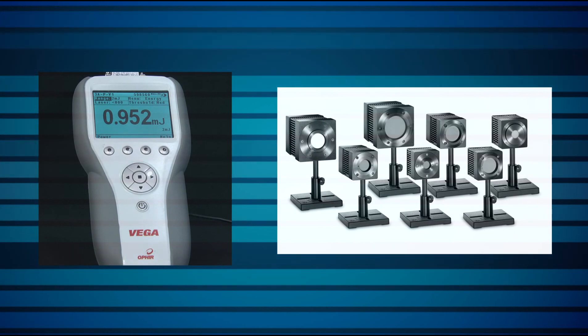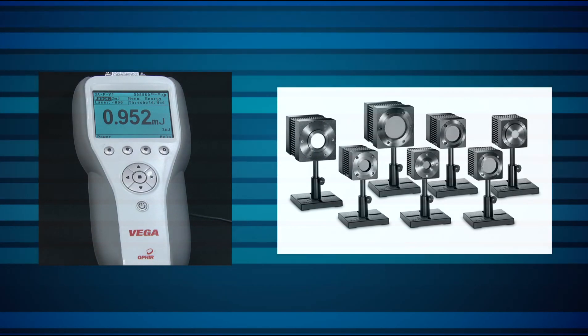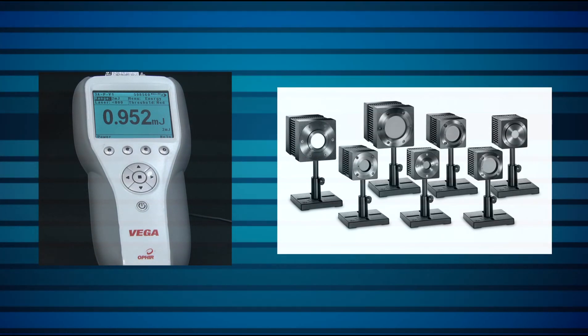But with many tens of joules per square centimeter zapping human skin, they can still do serious harm if the system's behaving even a little bit differently than it's meant to. Even in non-medical, unregulated cosmetic applications, there's a real need to regularly monitor the IPL's performance. Thermal laser sensors are a standard solution for measuring the energy of a single-shot pulse of light.